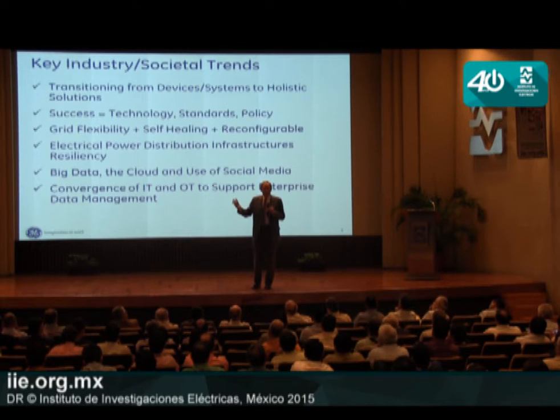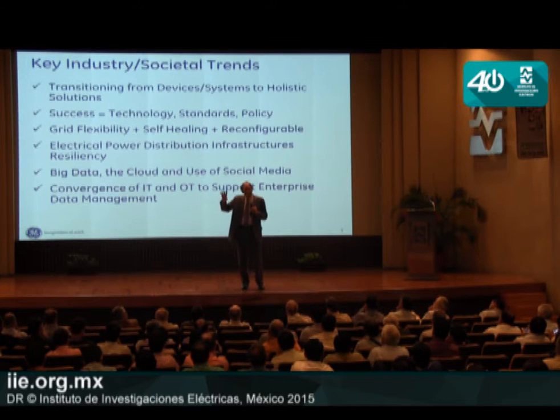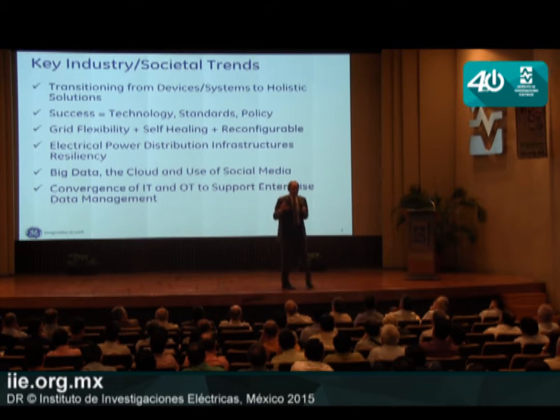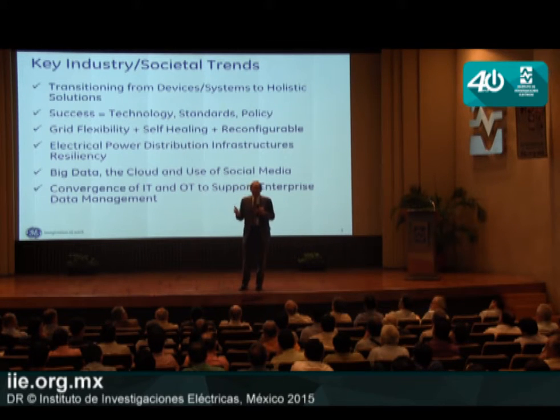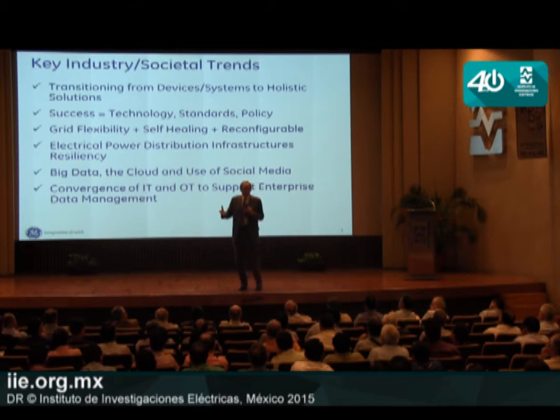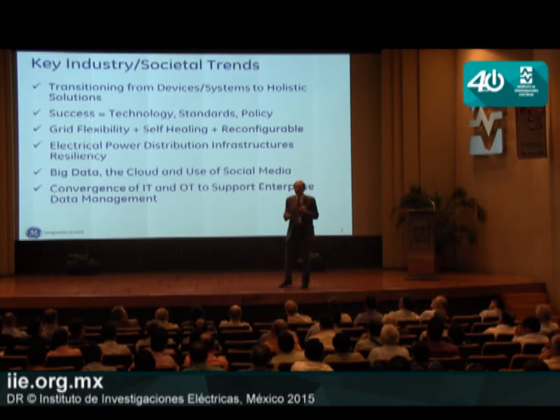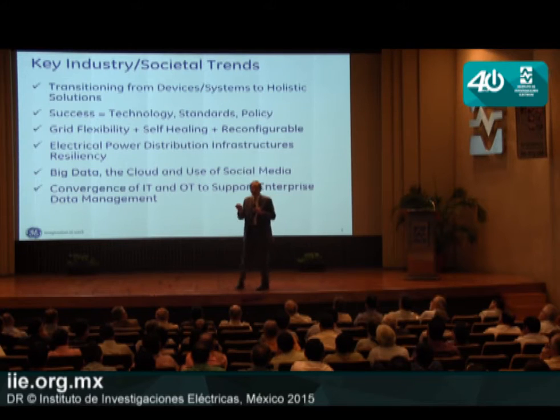Once we've tested the logic, we take the human out of the loop and close the loop on it. It's very difficult to improve the performance and reliability of the distribution system if you keep humans in the loop, because when calculating reliability indices like SAIDI, the duration of outages, and SAIFI, the frequency of outages, humans in the loop extend the time it takes to make decisions and carry them out. Once tested, closing the loop lets us detect a fault, isolate it, and restore service within a minute or two.